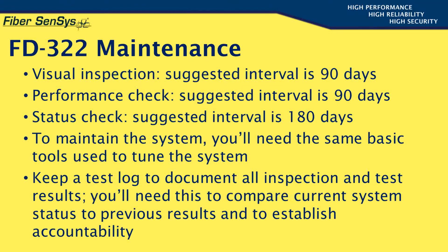The only new requirement is a test log in which to document all inspection and test results. The test log is an important tool that enables you to compare current system status to previous results. However, its most important function is to establish a clear record of accountability to prove that the system has been consistently maintained in satisfactory operating condition. For your test log, choose a bound notebook with numbered pages to assure that pages cannot be torn out or added without evidence of tampering.